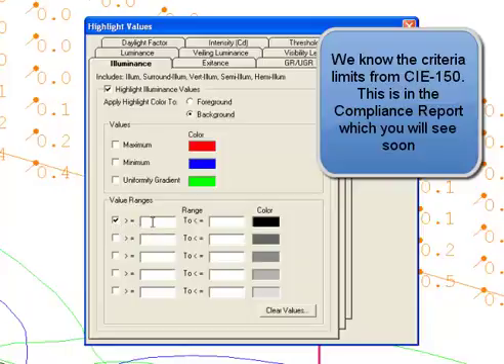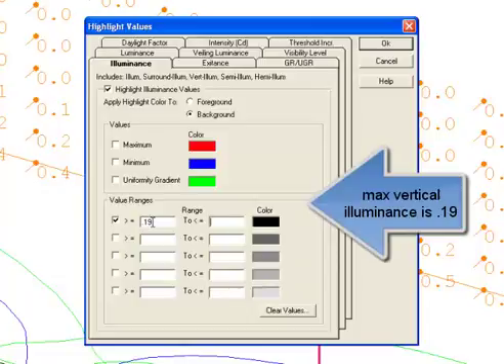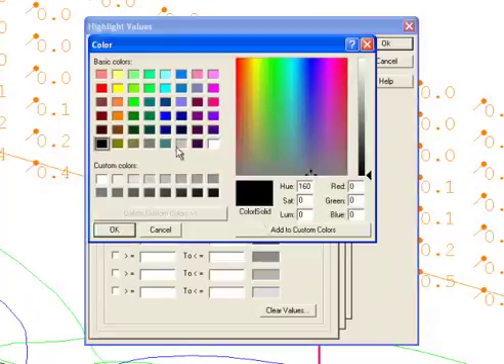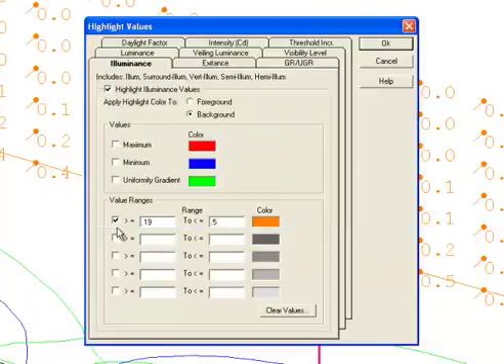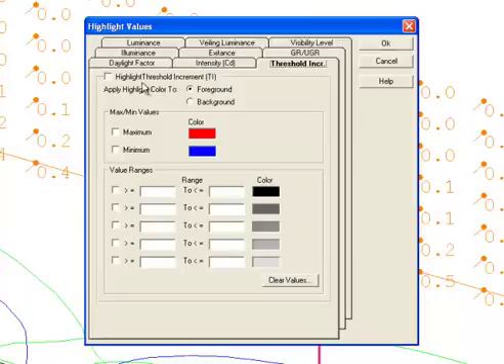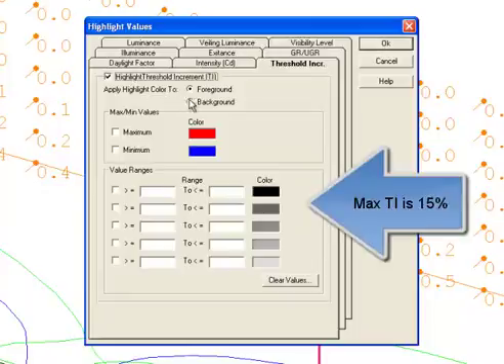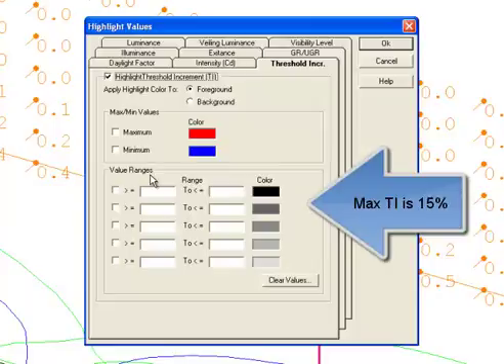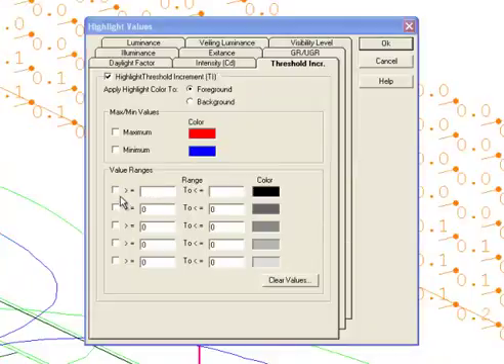We know the criteria limits from CIE 150. This is the compliance report, which we will see soon. The max vertical illuminance specified in CIE 150 is 0.19 footcandles. We'll see all those points showing up in orange as a background of orange.